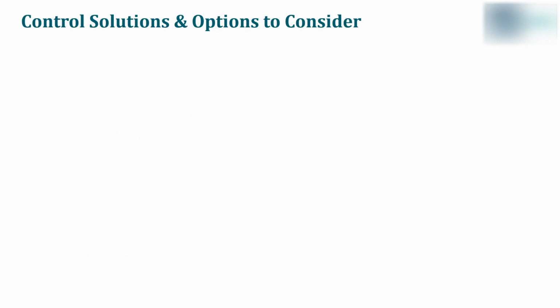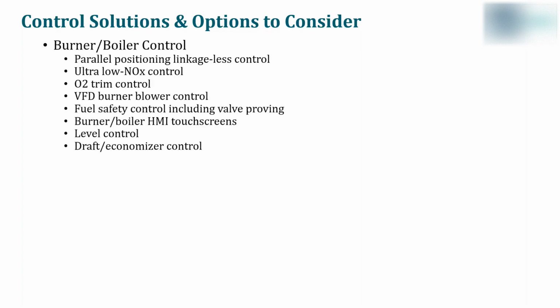Now, the goal of this webinar is to educate the customer on the information that is required to quote a system and have no surprises when that equipment arrives. When we examine the control solutions and the options on these pieces of equipment, there are quite a few things one has to consider before a system can be quoted. For the burner boiler control: parallel positioning linkageless control, ultra low NOx control, O2 trim control, VFD burner blower control, fuel safety control including valve proving, burner boiler HMI touchscreens, level control, and finally draft and economizer control.